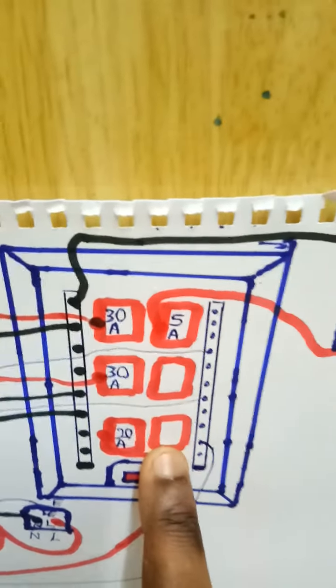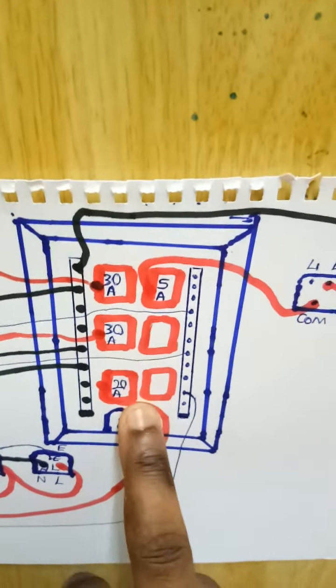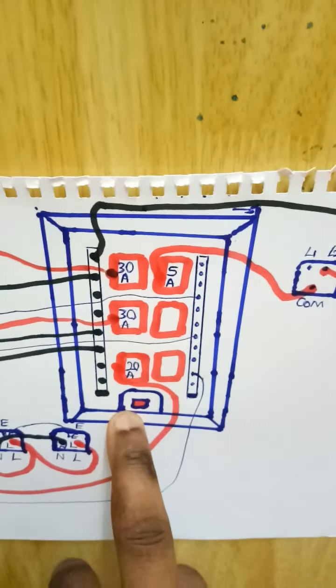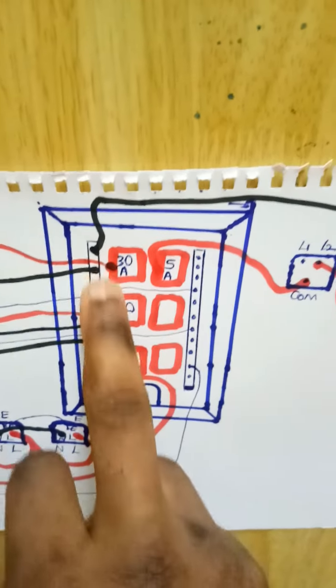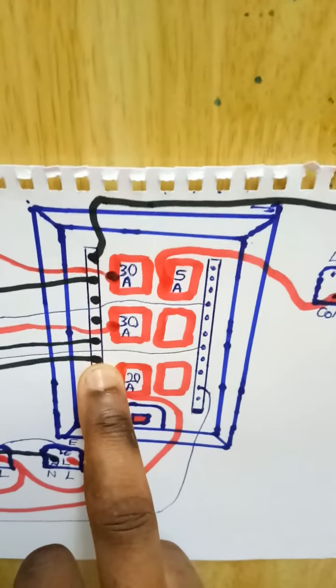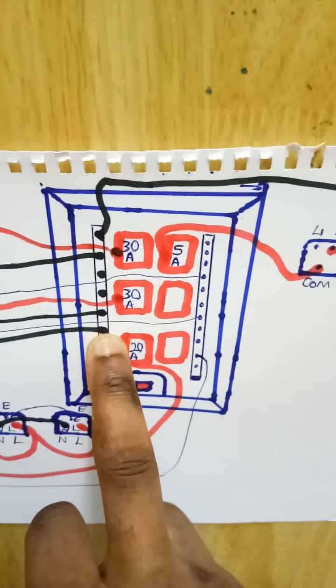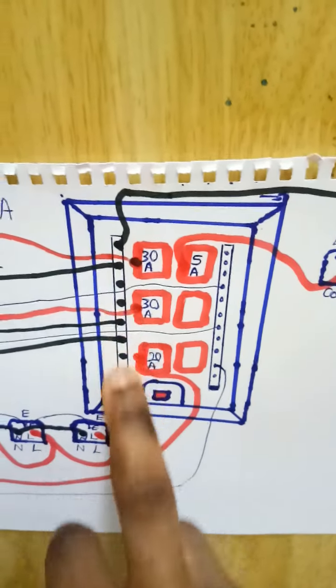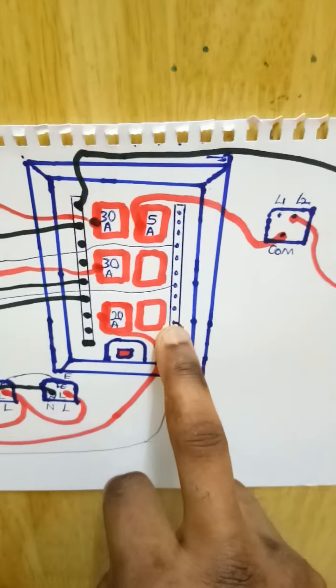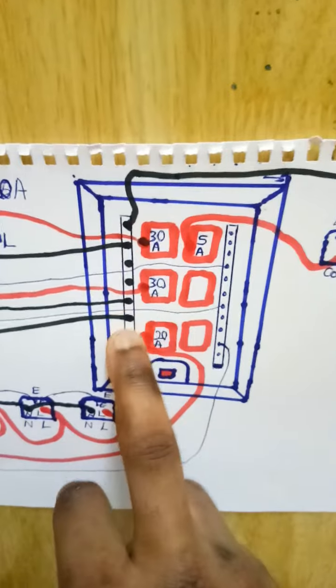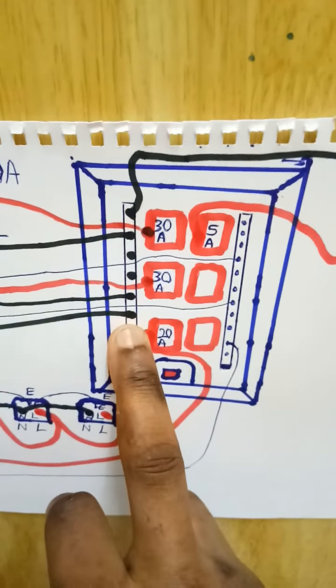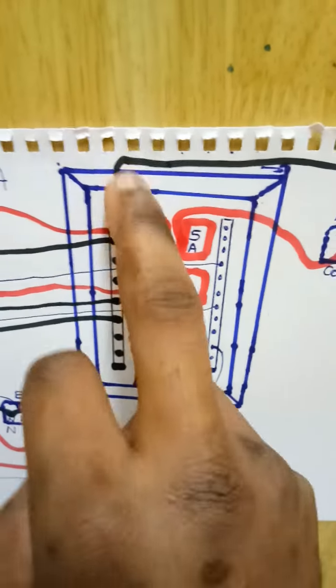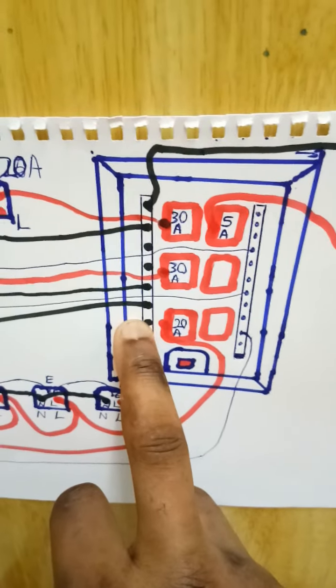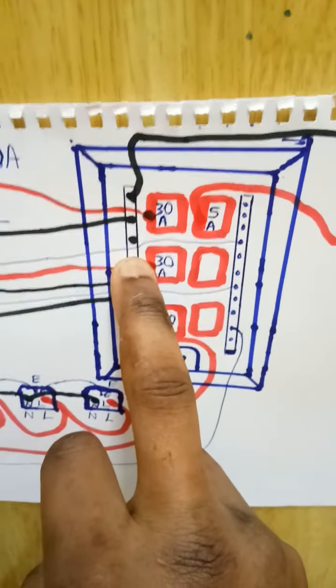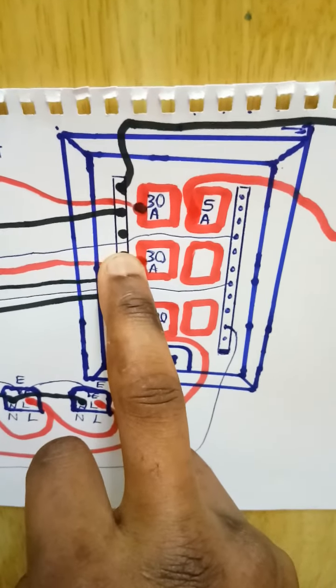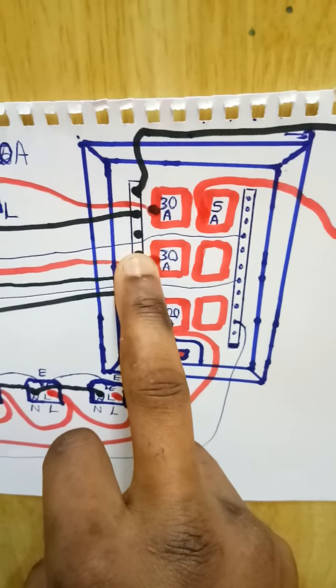As you can see, this is a representation of a distribution board. This is a 3-phase distribution board, and this here is a copper rail. An original distribution board must have copper rails. Some distribution boards have aluminum rails. This long line with a lot of screws is for connection of all the neutrals. It must be copper for it to be an original distribution board, because an original distribution board uses copper rails.